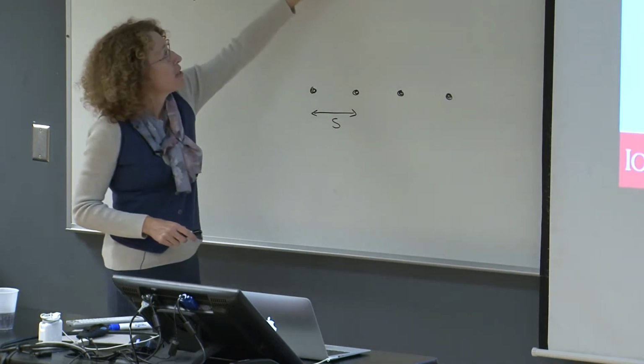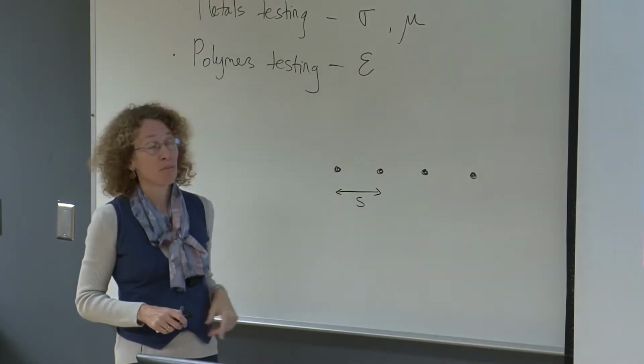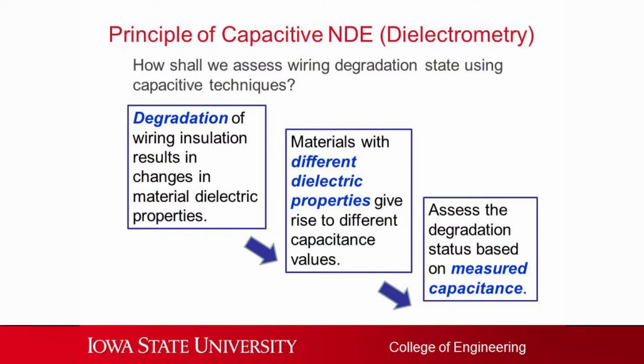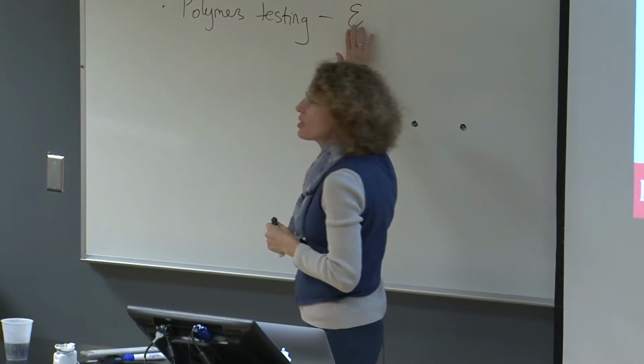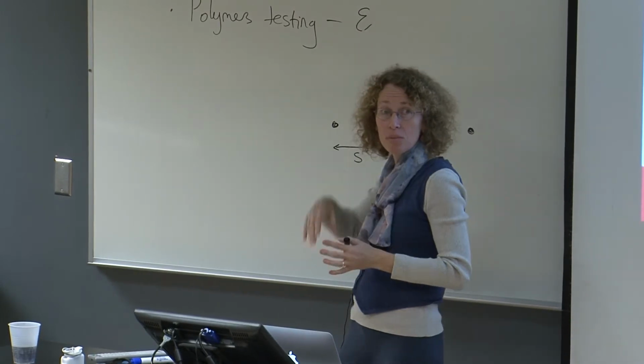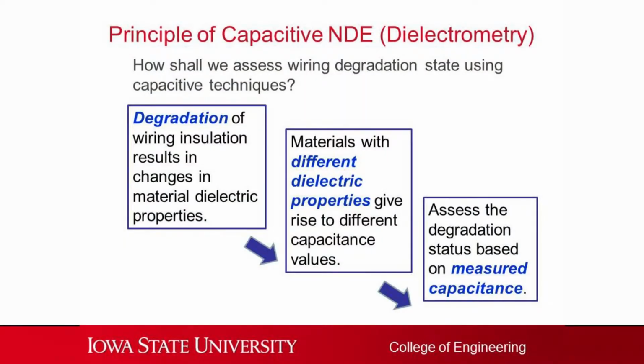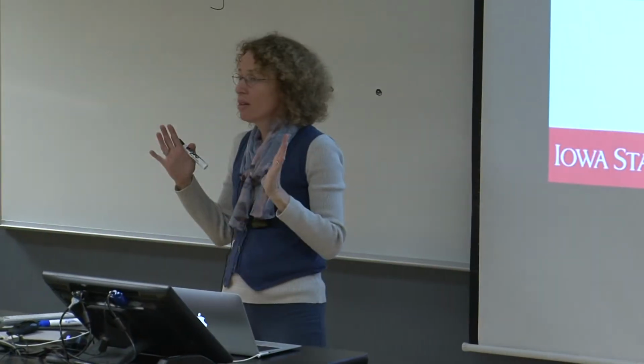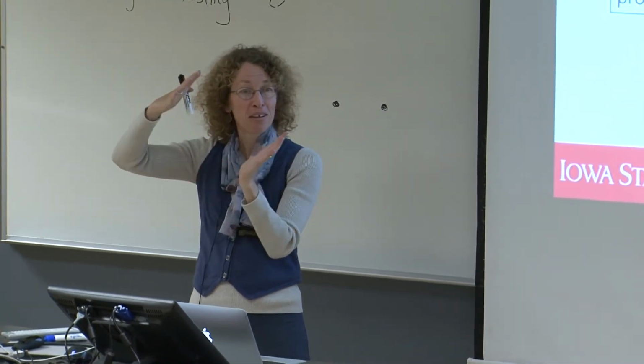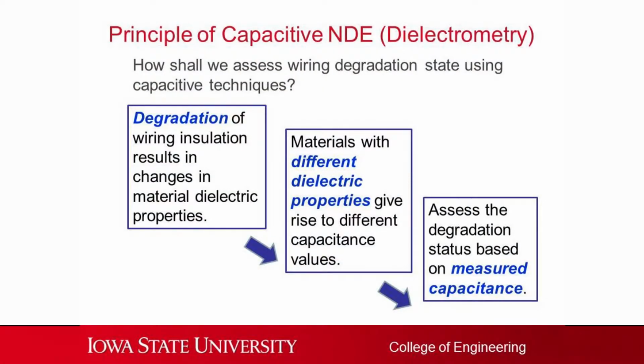So now we're not dealing with metals, we're dealing with permittivity, the parameter we want to probe. How can we do that? Degradation of wiring insulation results in changing this property of the polymer — it's often a polymer these days. If we change that dielectric property, we can measure it using a capacitor. We're all familiar with the parallel plate capacitor, with a dielectric between the plates that changes the capacitance. So if a wire's polymer properties are changing, you can measure that through a change in capacitance as well.